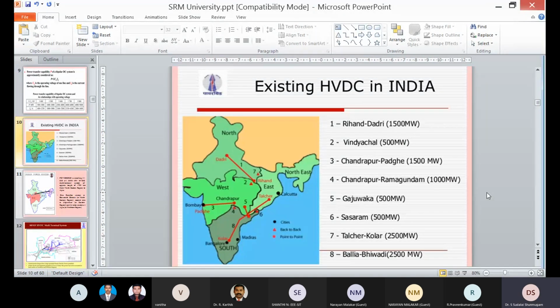So India has its own bipolar systems. The nearest one is in Kolar in Karnataka, Kolar to Talcher. Rihand, Dadri, Vindhyachal, and all other places we have. And one of the significant steps we have taken is moving to multi-terminal HVDC systems. So far, I have shown the 8 transmission lines which you are seeing. All belong to HVDC transmission, bipolar lines. India also has around 15 back-to-back stations right now. All are operating. We have 15 back-to-back stations to integrate our systems.